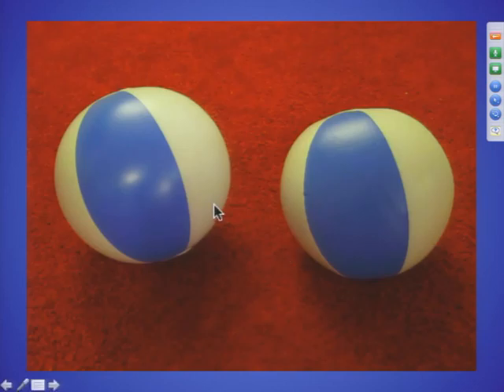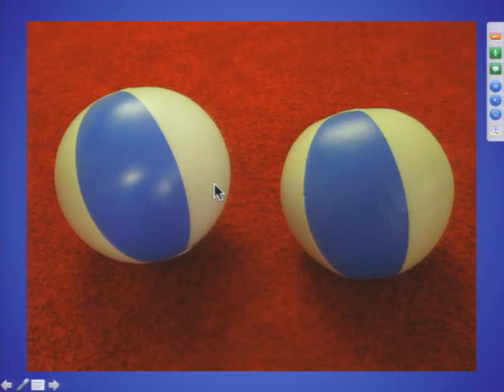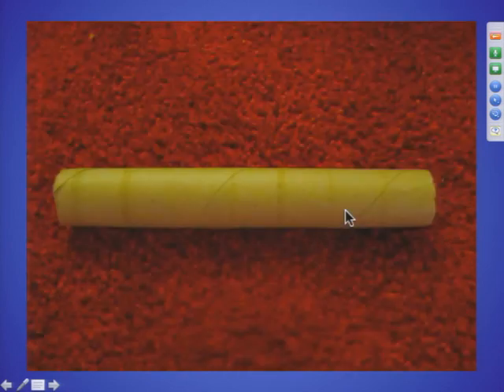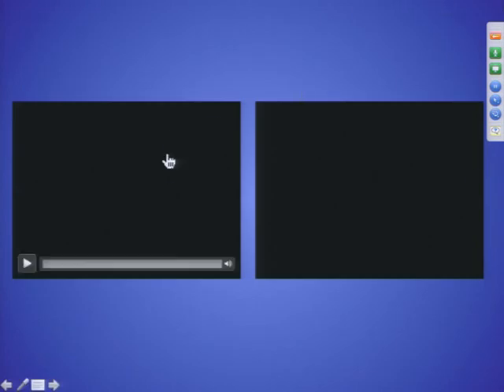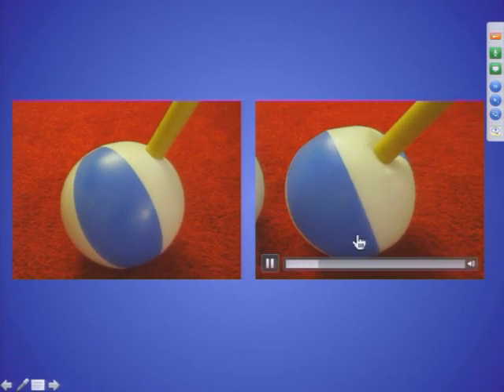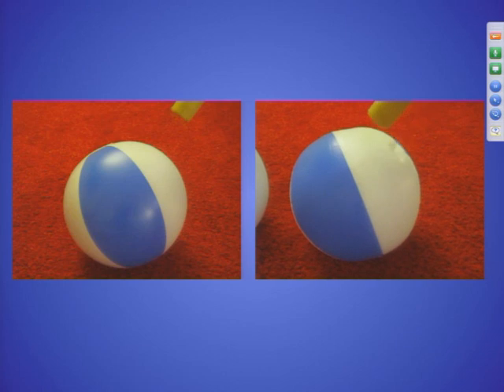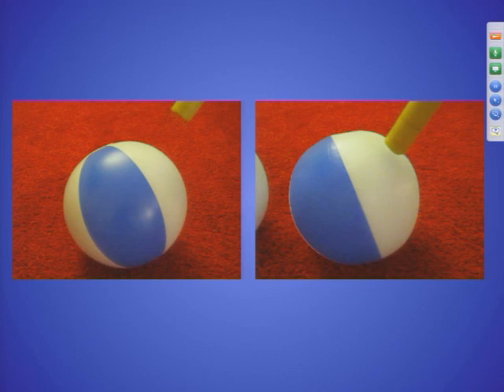This is actually the principle of applanation. Here are two balloons: one is overinflated, with higher pressure, and one has lower pressure — you can see the wrinkles. This is the measurement tool. For the balloon which is overinflated, you would have to apply a very strong force in order to flatten the surface. As opposed to the underinflated balloon, where even a very gentle pressure would create applanation and flatten the outer surface at that specific area.